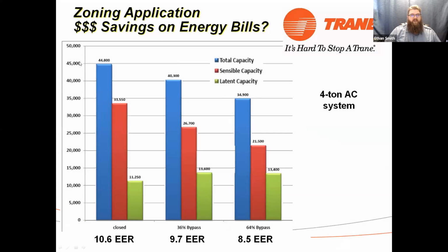Okay. So here's what it does for your energy bills. Remember, we talked about that capacity of our indoor coil going down as my bypass was running. Okay, so here's my efficiencies. I got a 10 EER system with that bypass closed. My 10 EER with the bypass closed, 36% bypass, it drops to 9.7. 64% bypass, it drops to 8.5 EER on a 4-ton AC, single stage unit.